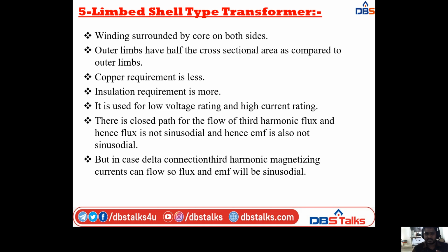Here there is a closed path for the flow of third harmonic flux. In the three-limbed core-type transformer, there is no closed path for the flow of flux, but in this one there is a closed path for the flow of third harmonic flux, and hence the flux is not sinusoidal. In the three-limbed core-type transformer, the flux and EMF are sinusoidal, but in the five-limbed shell-type transformer, the EMF is not sinusoidal.